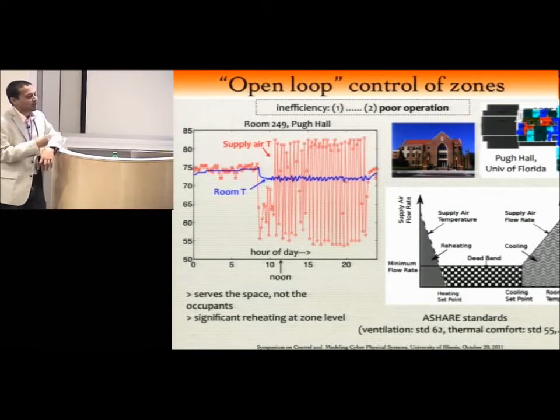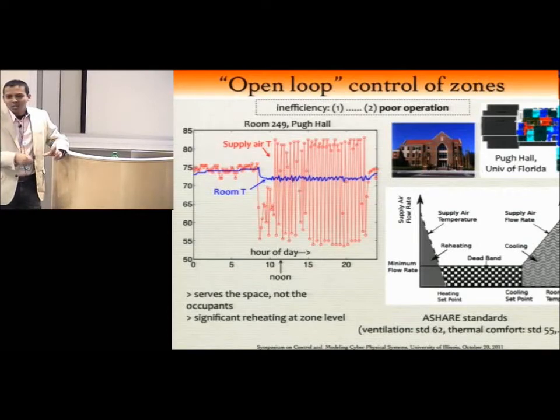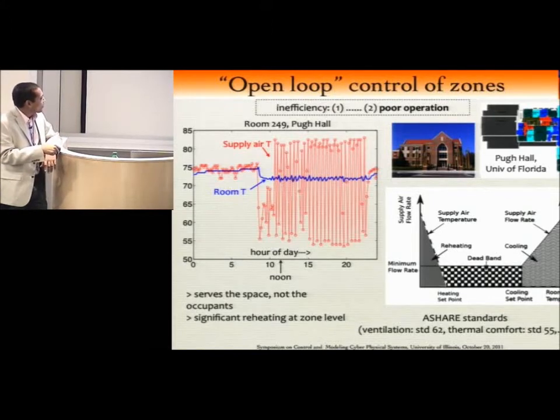This is one of the ways in which commercial buildings differ from residential buildings. You might occasionally get these letters from your utility, I get it all the time. The way to save energy is crank up your thermostat by 2 degrees in the summer. Well, here, if you increase the set point by 2 degrees in the summer, guess what's going to happen? It's going to do more reheating. So you'll actually waste more energy because the air is supplied at 55 degrees Fahrenheit, right?